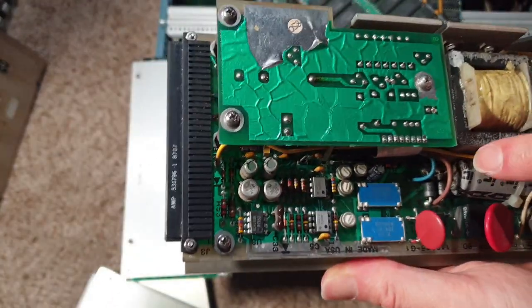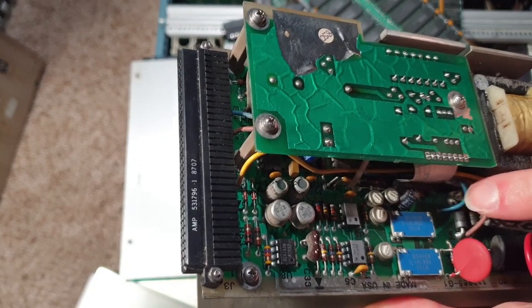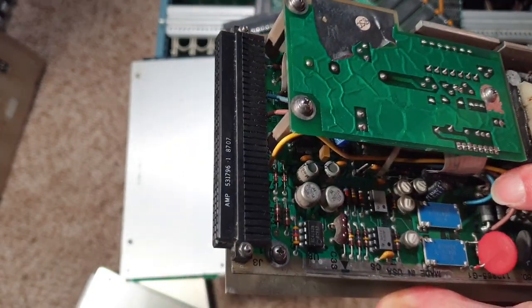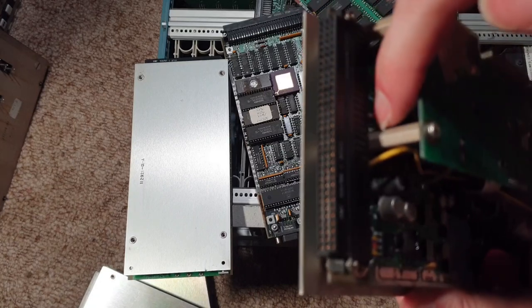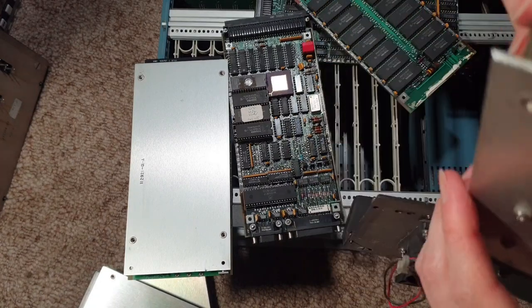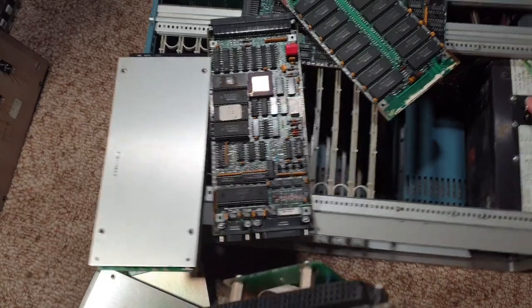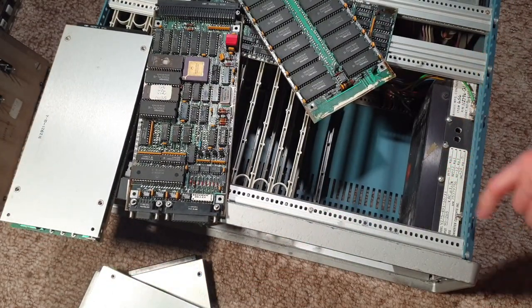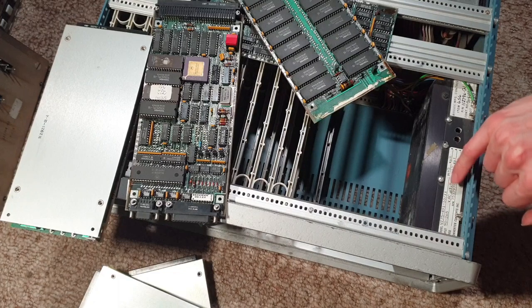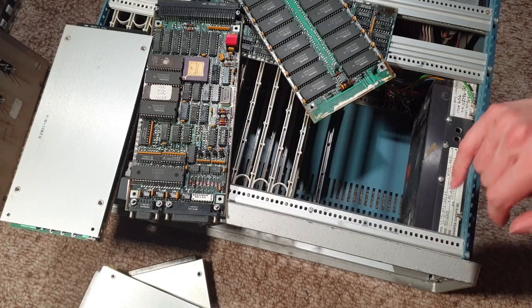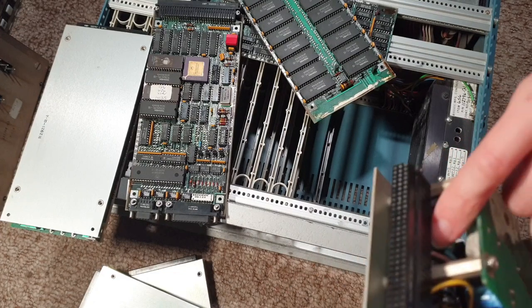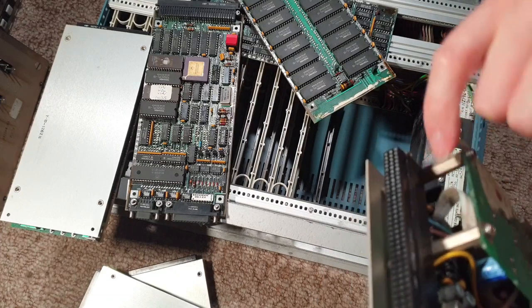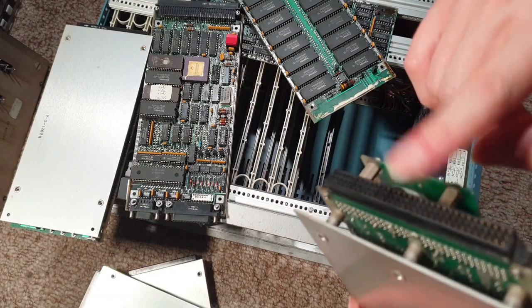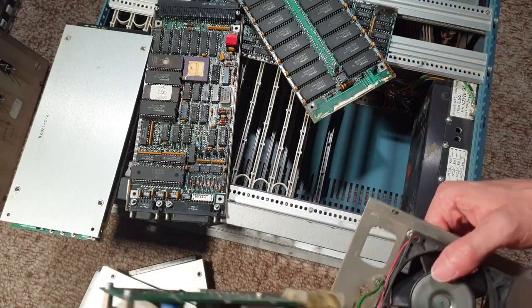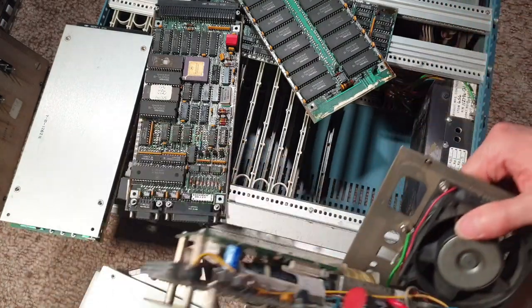But what's quite dodgy about this that I noticed was there seems to be, fairly sure that will be the high voltage DC from the mains going onto some wires that then go onto the DIN connectors and then must travel over. I have to, because here is another power supply which is a 90 to 265 volt AC input. So that has to be either the AC or DC high voltage going through the backplane through these. Which, yeah, I didn't think that was the sort of thing you do, but here it is being done.